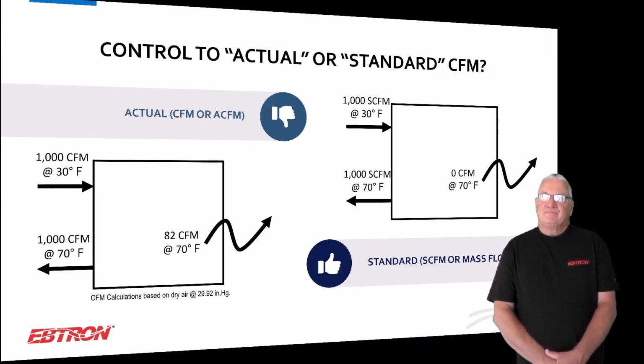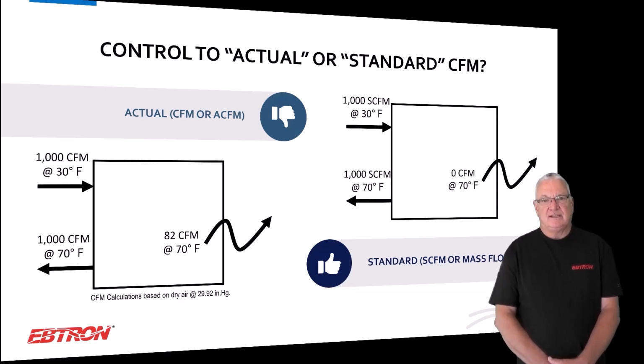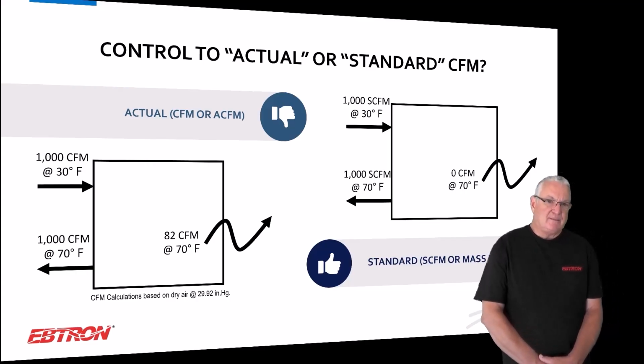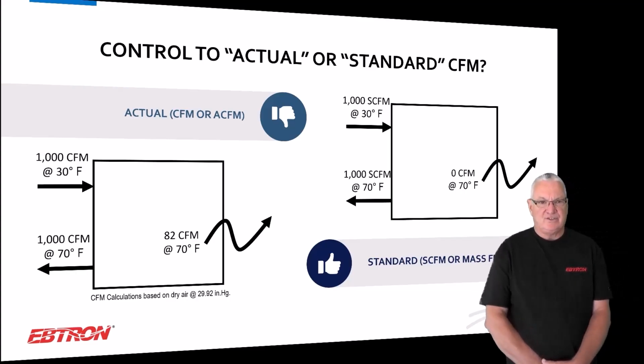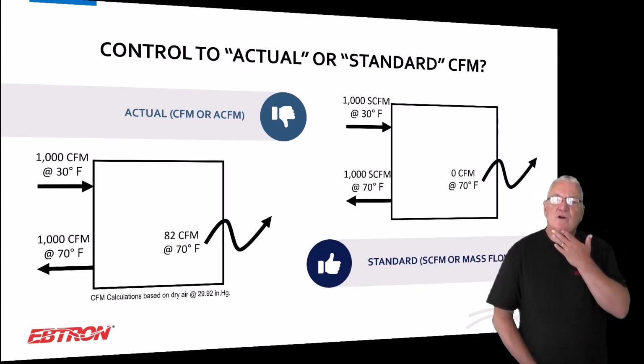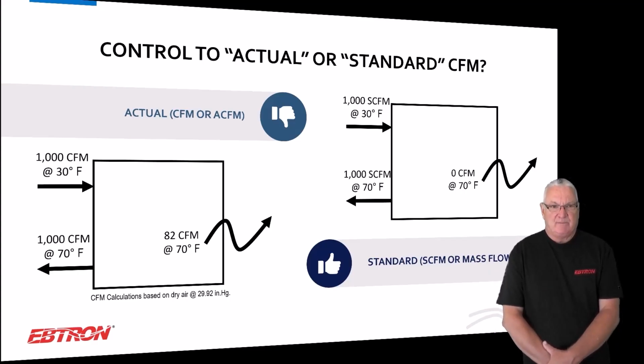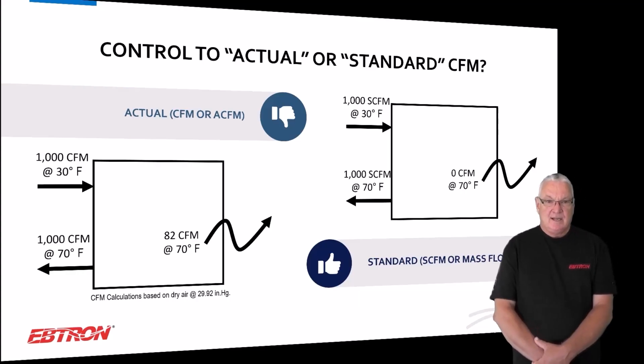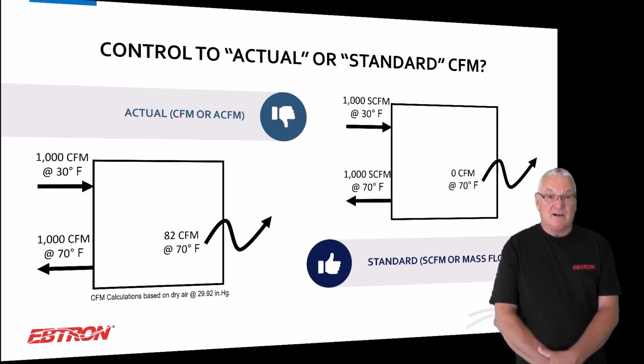That really doesn't make a lot of sense, because we have changes in air temperature where we're doing the measurement. We should be thinking more like the process folks and thinking in standard CFM, which is really a mass flow equivalent. And so what I've done here, I used this slide for a lot of different presentations. I could have tweaked it a little bit for this. This is really more of my outside air type of one. And when I talk to people about why Standard 62 isn't right, talking about calculating outside airflow rates and then coming up with a rate, and then you set it on one building when it's 10 degrees out, and you set it on another building when it's 100 degrees out. They're not the same flows, okay?